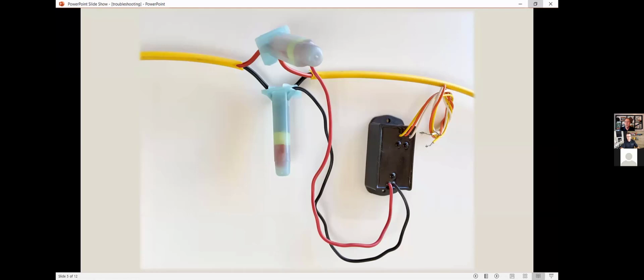Maybe Dan, when there's this overcurrent, can you still water? Does the system function—what happens to the control system in that overcurrent status? In that overcurrent status, we can't do any watering, so it can be quite urgent, especially if this happens at the beginning. The controller basically shuts down, because there's a short out in the field with potential to damage it, and we don't want the controller damaged—so it goes into that shutdown mode essentially.